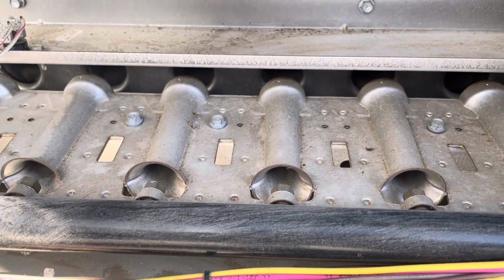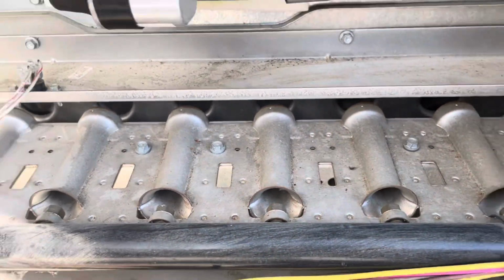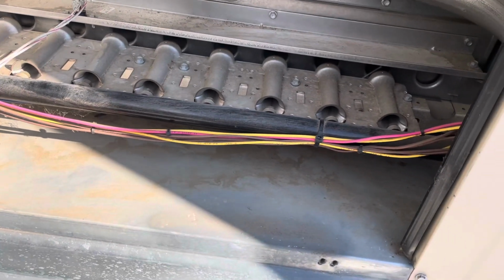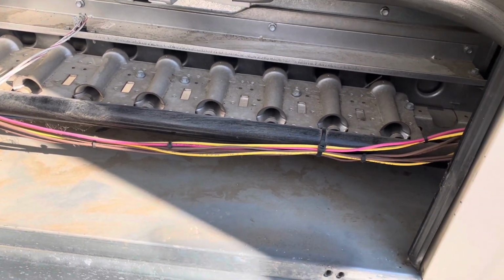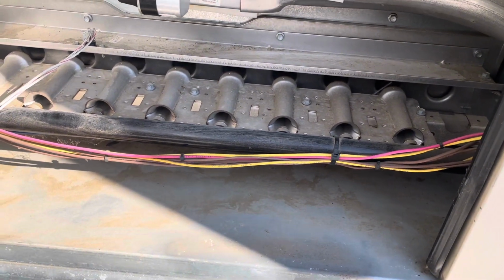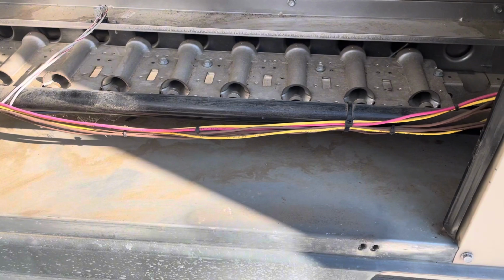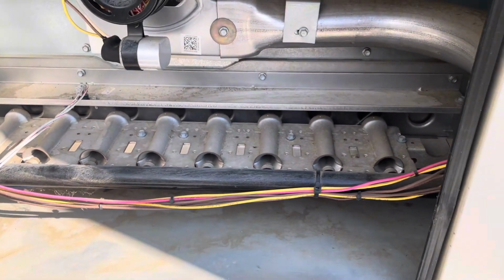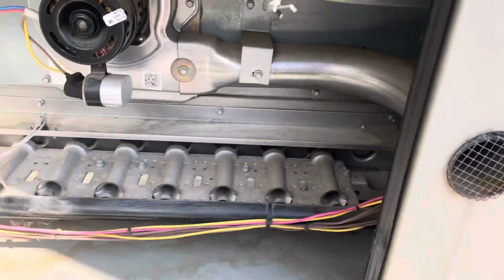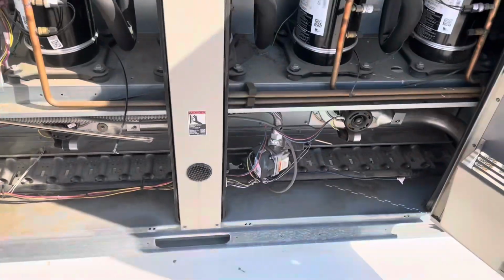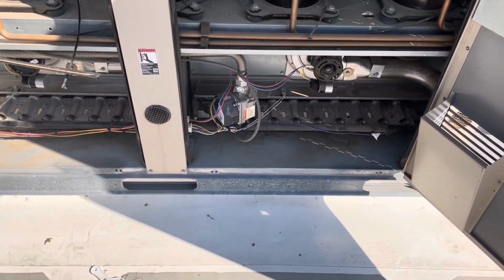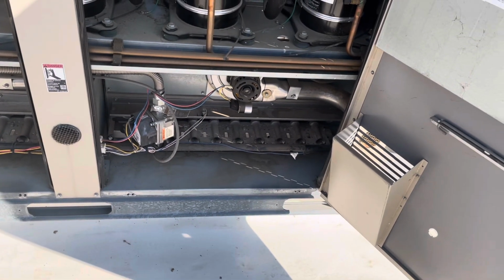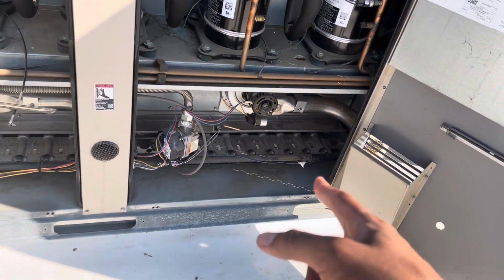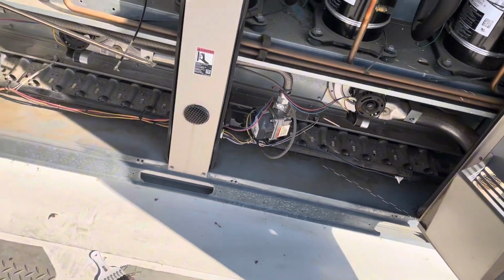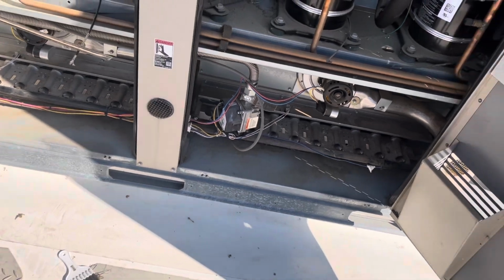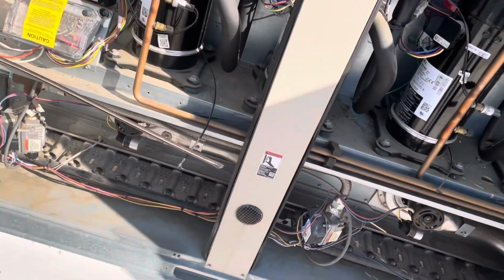And flame rollouts are pretty obvious. I mean, the flame is literally coming out. So that's a good indicator that you have a bad heat exchanger, if you don't check the heat exchanger before you turn the heating section on. So yeah, pretty straightforward. There's really nothing to it. The heating section is pretty easy. Like I said, I will make another video explaining how to check DC microamps for the flame sensor. So like I said, pretty simple.